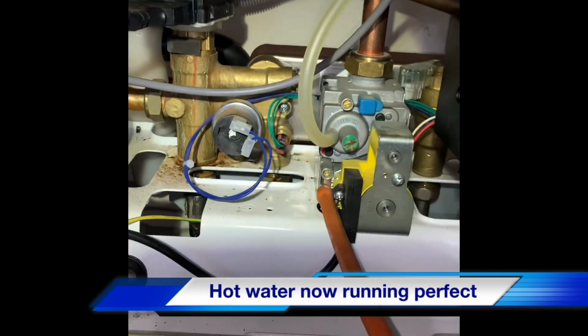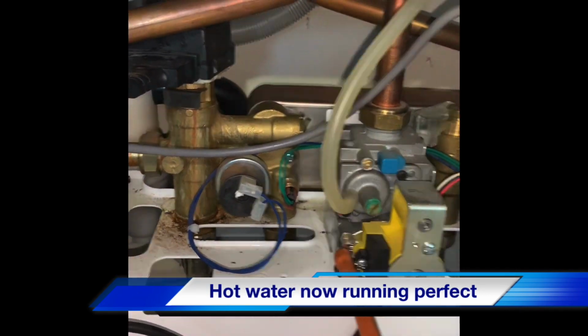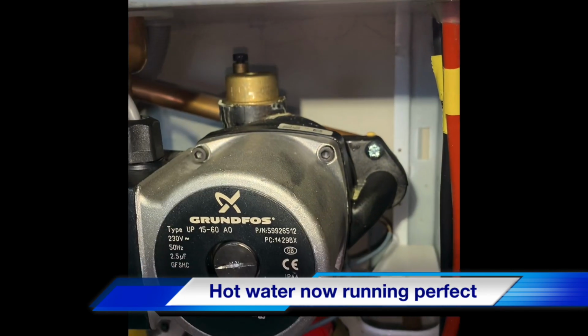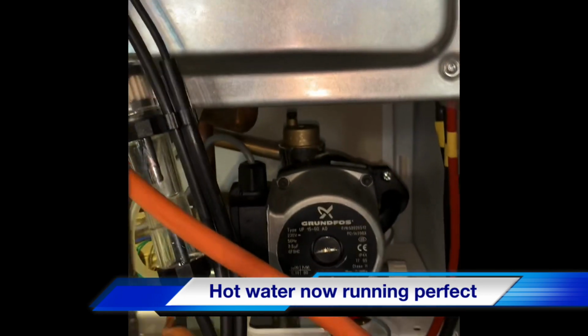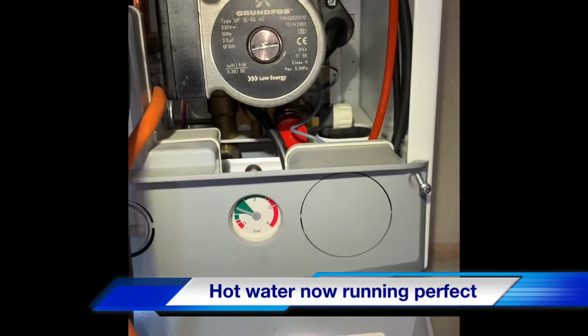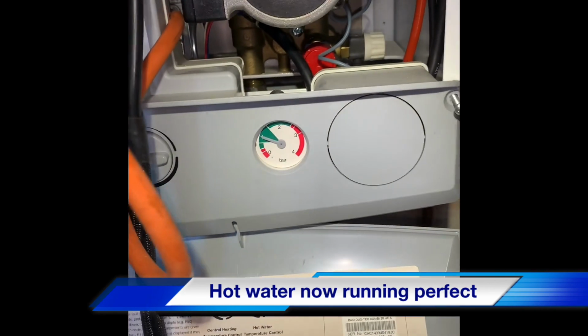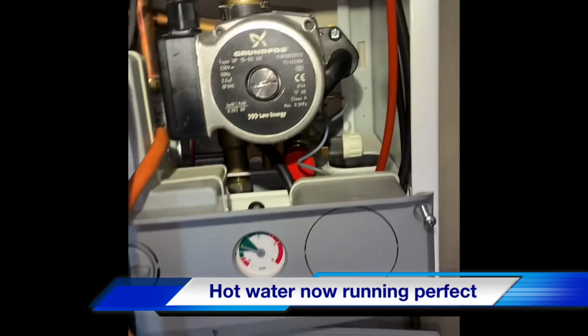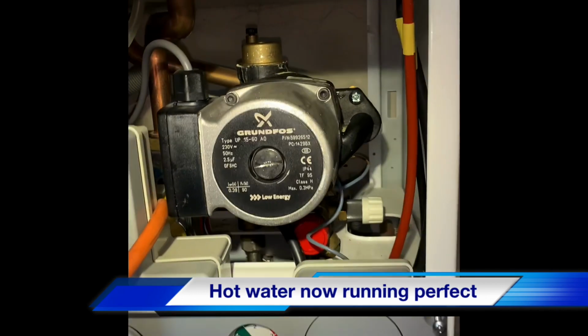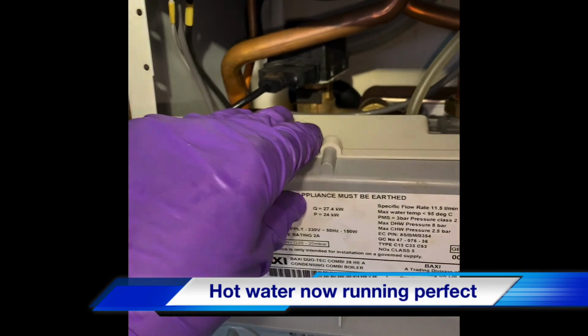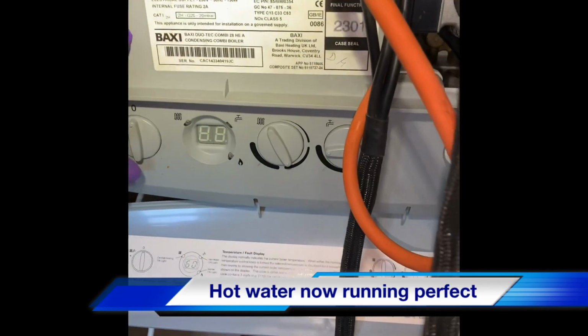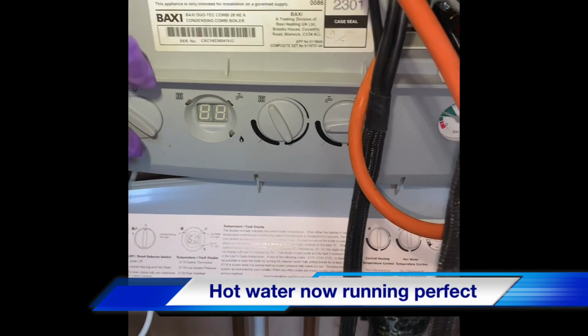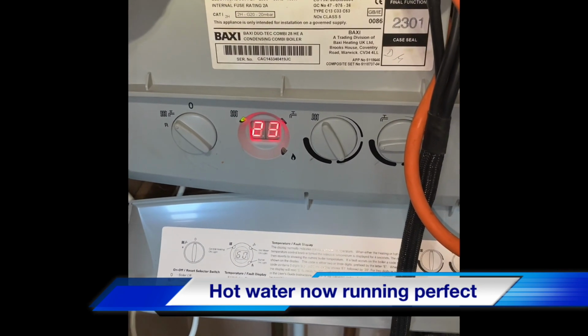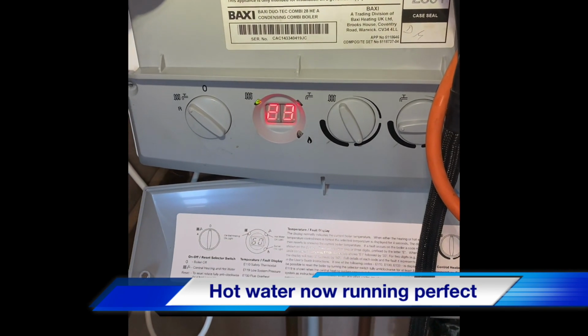Right, so we have replaced the diverter valve cartridge, we've replaced the plate heat exchanger, we've replaced the auto air vent, we've recharged the expansion vessel, and we've refilled the system to approximately 1 bar water pressure. Prior to taking the components out, we checked the pump function and voltage. We also checked the diverter valve function and voltage. So let's turn this on for the first time, and we'll see what happens when we run the hot water this time.